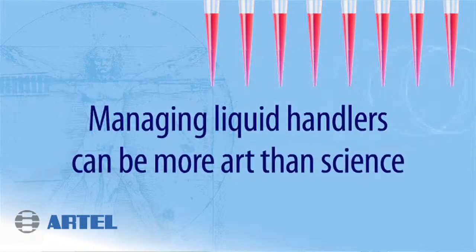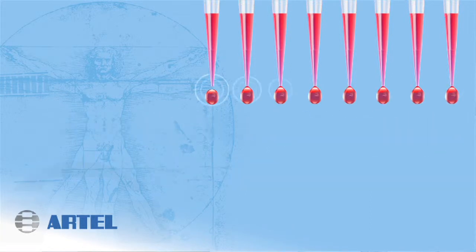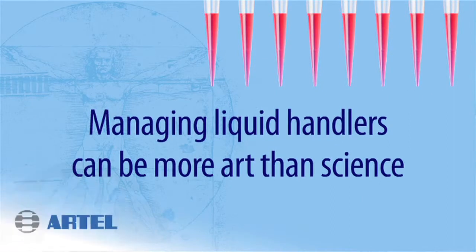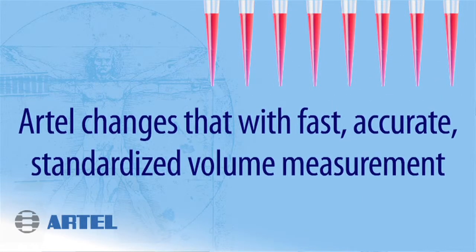Typically when people calibrate their liquid handlers they do that in an aqueous environment, and they see very often that when they dispense their compounds in DMSO they're seeing a difference in performance of their liquid handlers. So using the Artel MVS — the system here — we allow people to calibrate their liquid handlers in the environment that they would use them every day.